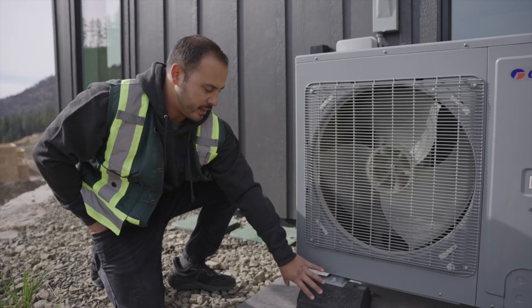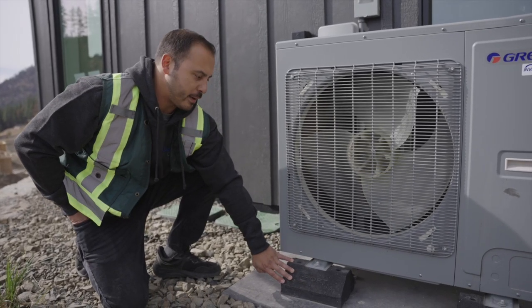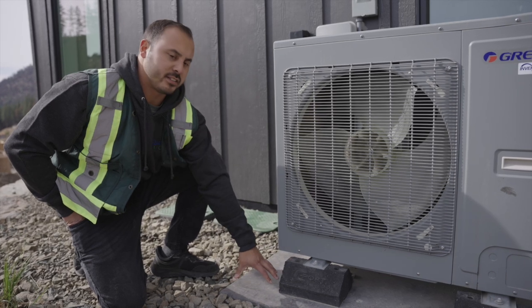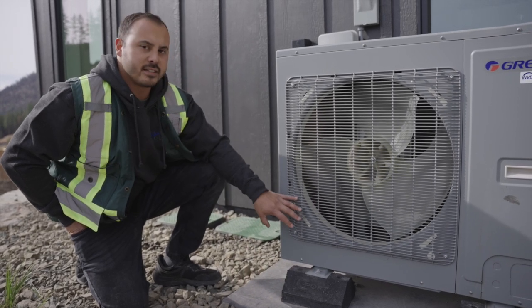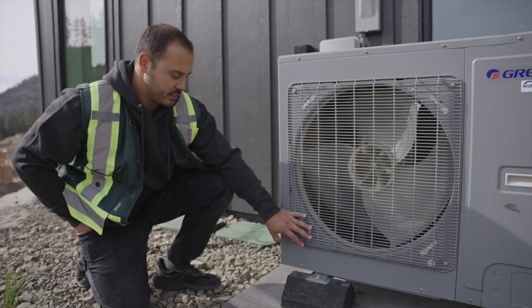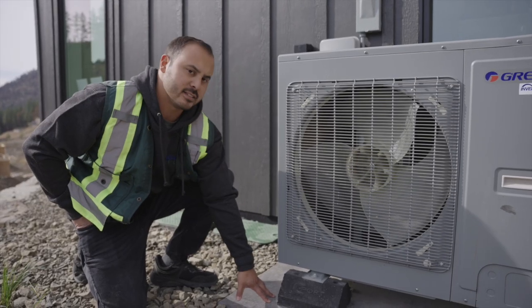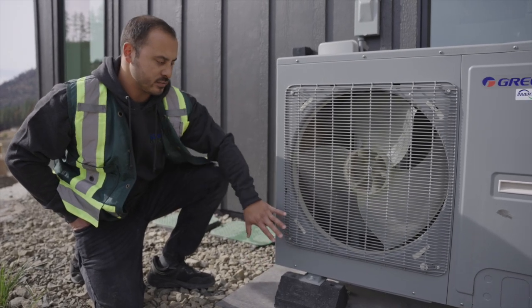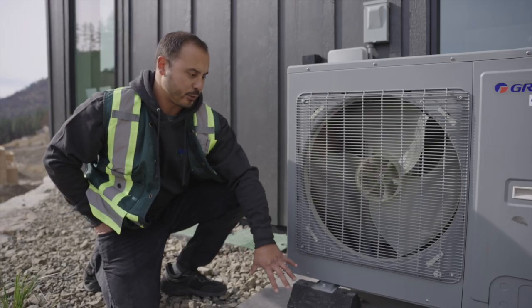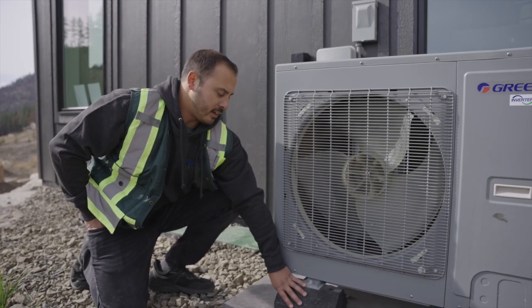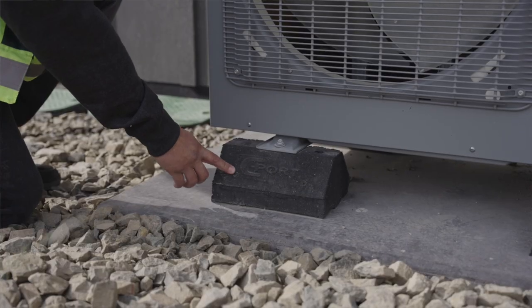It includes having an elevated surface that prevents the heat pump from actually touching the ground. If it's touching the surface during defrost cycles, it produces condensation, which would create an ice dam and a hazard outside. Our team has installed elevated blocks, as well as rubber isolation blocks, to prevent noise transfer around the building.